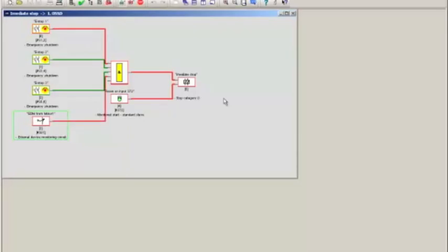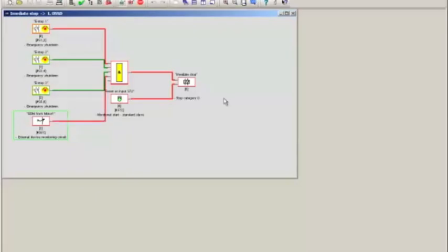So the proper way to address this scenario is in the real application, you would replace the faulty safety contactor, the faulty motor starter. In my case, it's much simpler. All I have to do is reconnect the wire that I took off and connect it to this S81 input, which I'm doing right now.